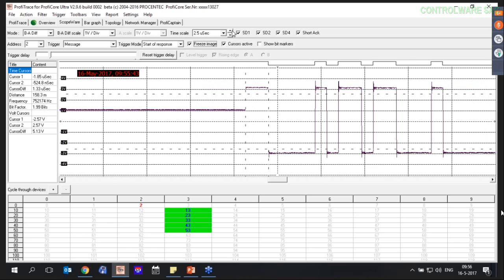But if I look at the smallest bit of my Profibus, I believe it's this one, I can see that my Profibus speed is 1.5 megahertz. So 1.5 megabits per second. And I can change this horizontal line. I can set it over there, and I can set it over there, and my program will measure the amplitude of the signal. So the amplitude of this signal is around 6 volts.